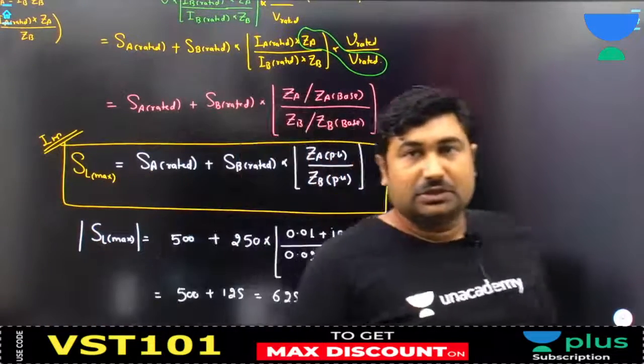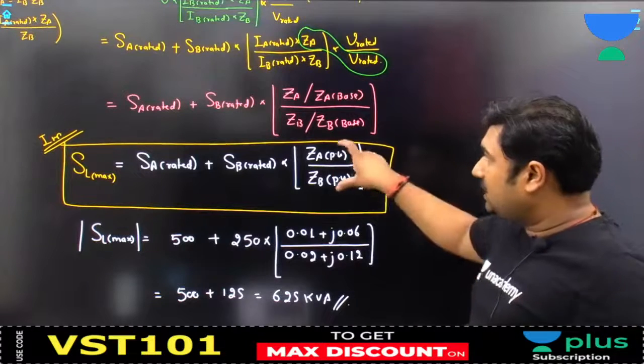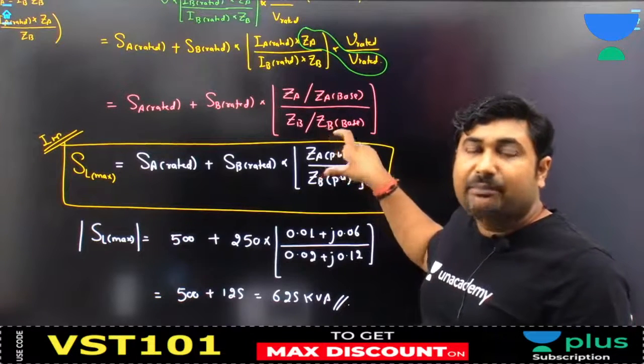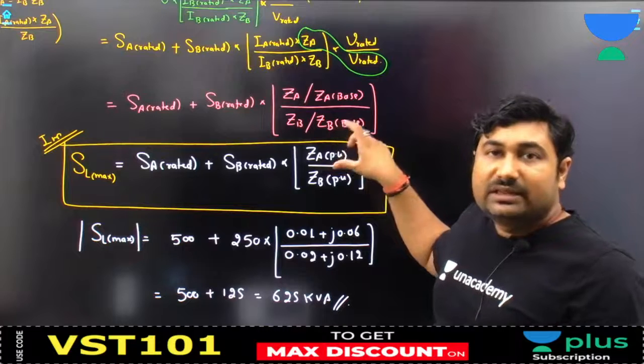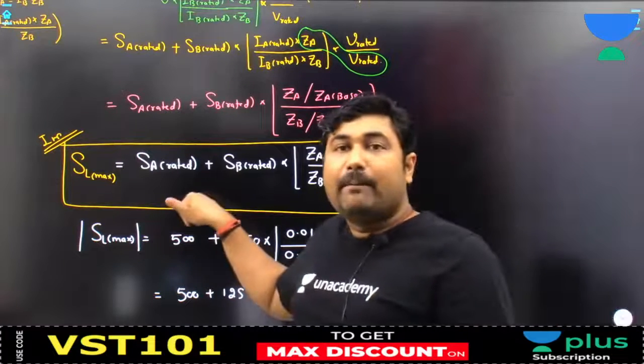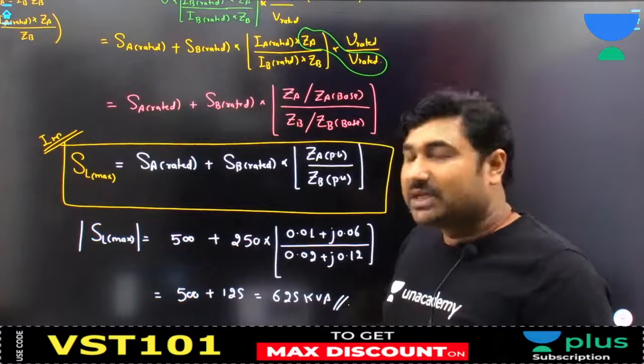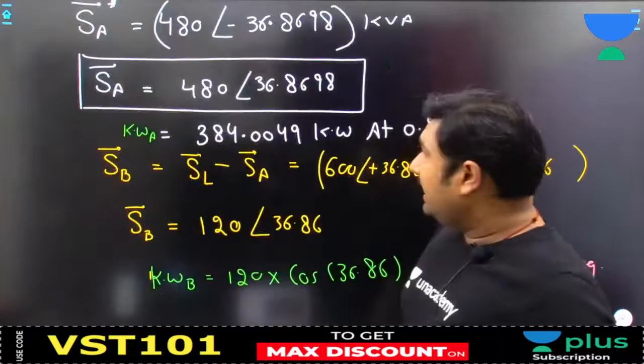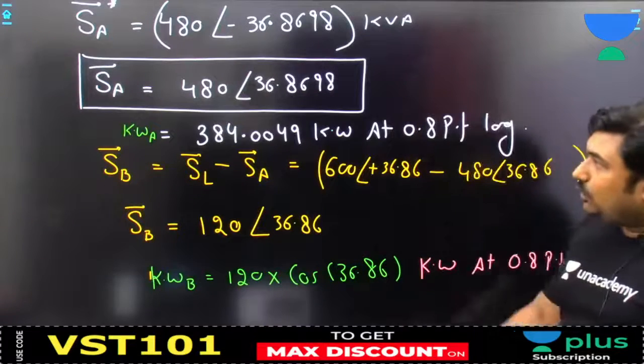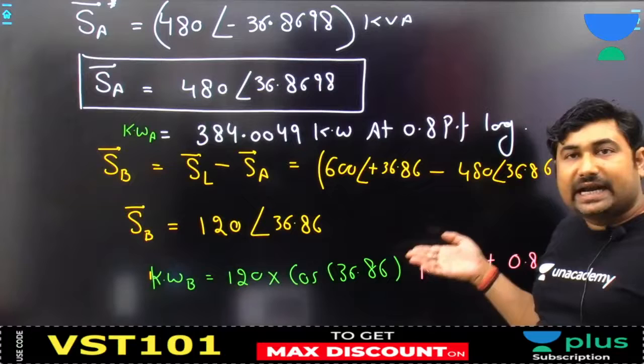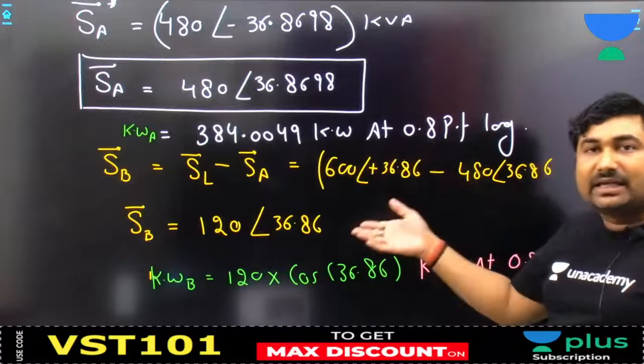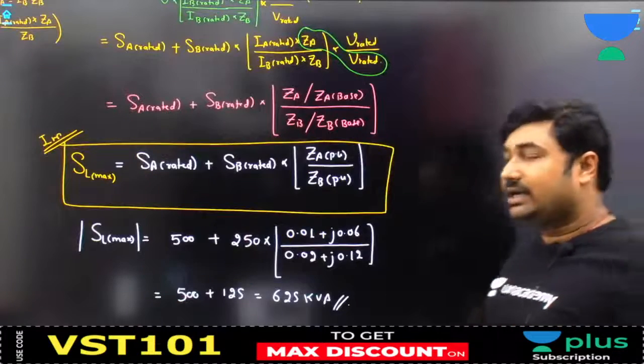Great, sir. So now we know that if the two transformers have the same per unit impedance on their own base values, they are going to share the load maximum. Okay, if the two transformers have the same X by R ratio, then both the transformers are going to operate at the same power factor, the same as the load power factor. I am hoping up to this part each and everything is clear.